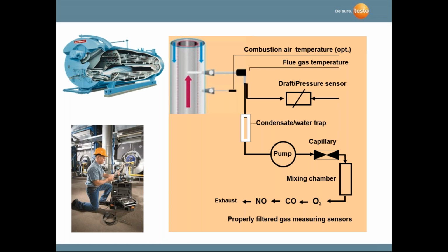So when we're doing a flue gas test, it's good to check your probe and hose assembly. Not only is the probe location in the stack important, but also make sure we don't have any leaks in our hose assembly. We do have a feature on the 300 called a gas path check, and I'll review that with you when we go over the operation of the 300.